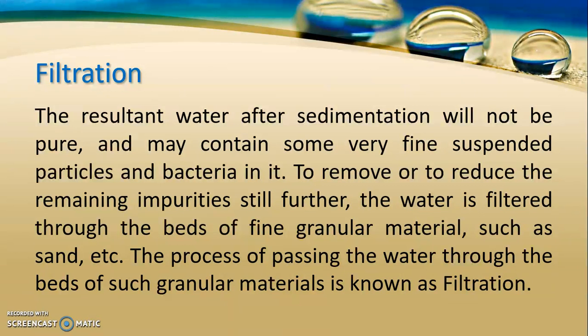The water after sedimentation will not be completely pure and may contain very fine suspended particles and bacteria. To reduce the remaining impurities further, the water is filtered through a bed of fine granular material such as sand. The process of passing water through beds of such granular materials is known as filtration. The filter bed consists of layers of sand and gravel, and water is made to pass through them to remove finer particles and bacteria.